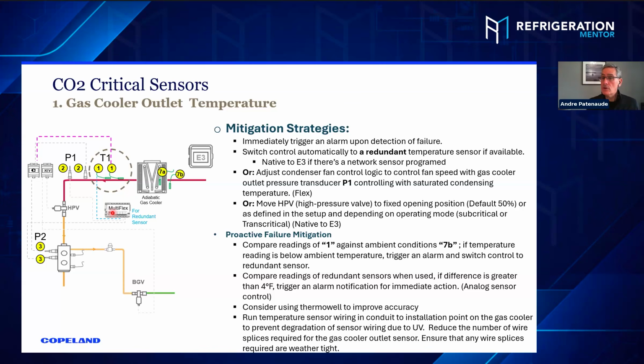But if you don't have that redundant sensor, this is where other mitigation strategies come in. Or adjust the condenser fan speed logic to control fan speed with gas cooler outlet pressure P1. Now that's going to be controlling off of a saturation temperature. So a little bit different, but you're going to limp along and still let the system run. It might not be as efficient, but the alarm's gone out. The system is still running, and you have to build that flex combiner because now you're controlling off of a saturation temperature.